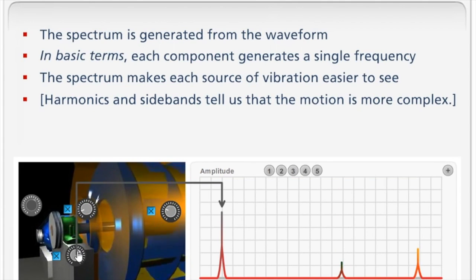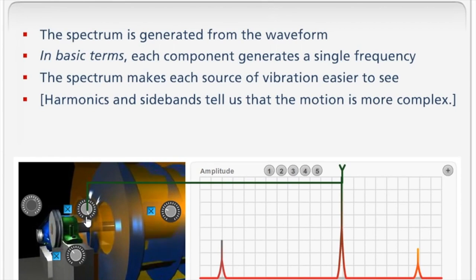So basically I might take a measurement one day, and let's just say it looks like this. Whoops, I turned that too far didn't I? So it might look like that. No green vibration, a little bit of gray, a little bit of orange. Now of course, in the vibration world, we would just say that's 1x and 10x.